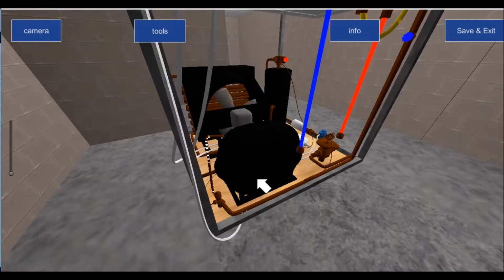Sometimes you'll find that they just rattle on startup and they smooth down after a while. Sometimes you might need to look at the mounting. So again, there are usually rubber mounts on the base of these types of compressors that they're sitting on, and that's to allow for the reciprocating motion as well. So you may need to look at that and make sure that the rubbers that they're mounted on are all evenly the same height. Sometimes you might find there's a rubber missing, and that could be causing your rattling. Other times you might find that one of the rubbers has started to deteriorate and the compressor is slightly lopsided. That could be causing the rattling as well.